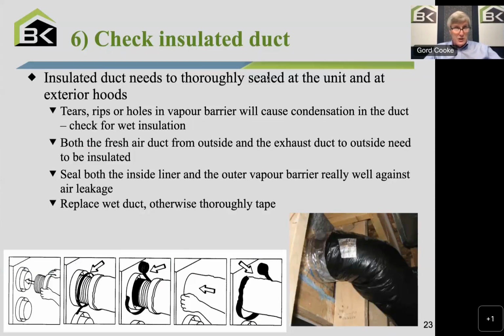Let's say they were doing some work in the basement and somebody happened to damage the duct. If you feel the duct and it's wet inside that liner, that means there's a hole in the liner. So you don't want any tears or rips or holes in that black liner, because that'll cause condensation in the duct. So both ducts, the fresh air and the exhaust air, have to be insulated, but you want to make sure they're properly sealed. And if you find the duct is dripping, that's because there are rips or holes or tears in the black liner. Typically, that means the duct has to be replaced.